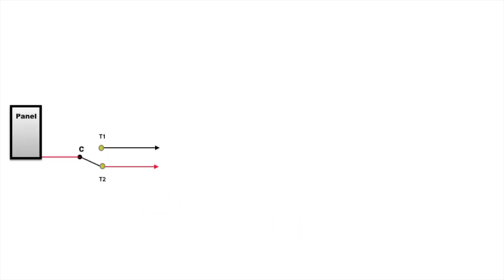Let's go ahead and throw another one in, because with three-ways, there's always two. You can see that we've got two of the three wires hooked up to the second three-way switch on the right. The traveler wire coming from the first switch hooks up to the traveler terminal on the second switch, both top and bottom. So you've got the common wire on the left coming from the panel. What does the common wire on the right hook up to? You guessed it. It goes to our load, which is in this case a light bulb.